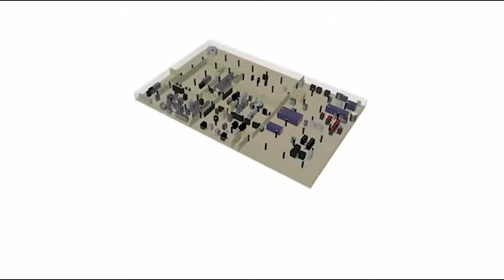So in this example, we have a client that wants to install some new high density equipment. Now, depending on how old the data center is, this density of equipment may not have been considered when the data center was planned. So you may have planned for 3 or 4 kilowatts per rack, and suddenly you're being asked to install 5 or 6 kilowatts per rack in a vendor configured cabinet.